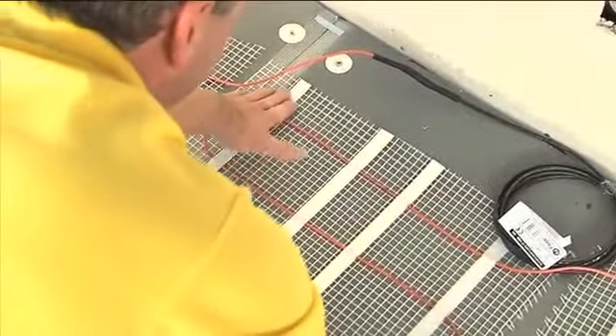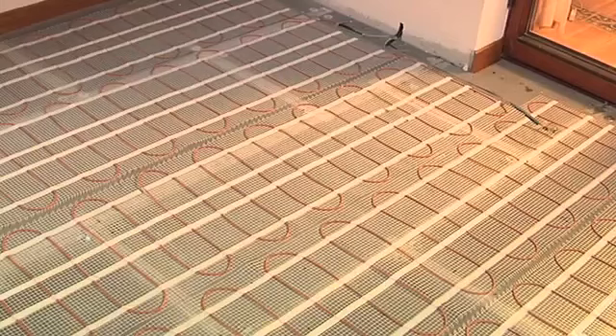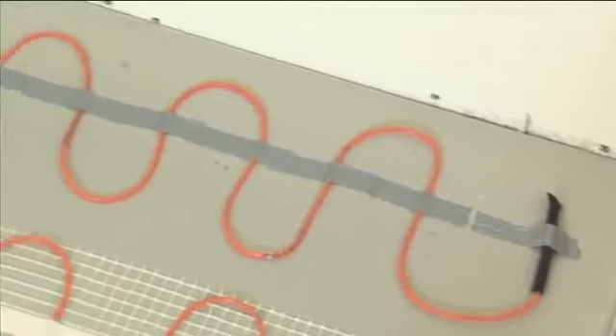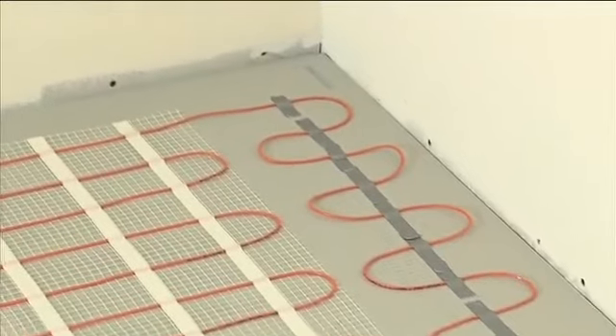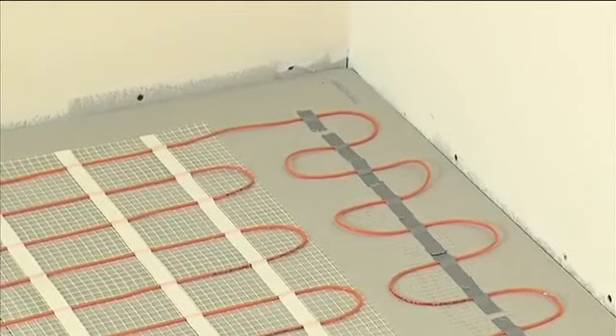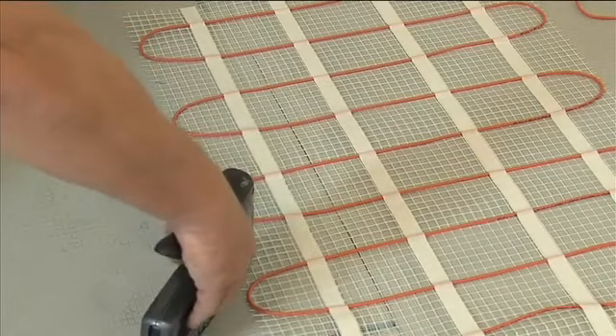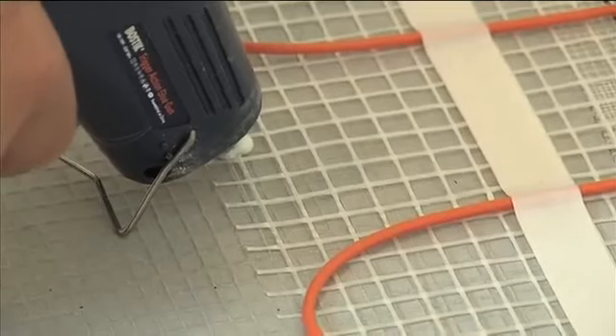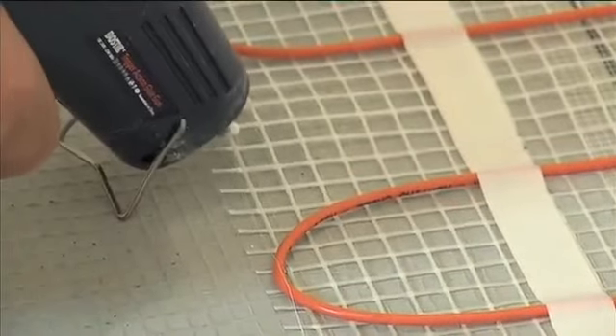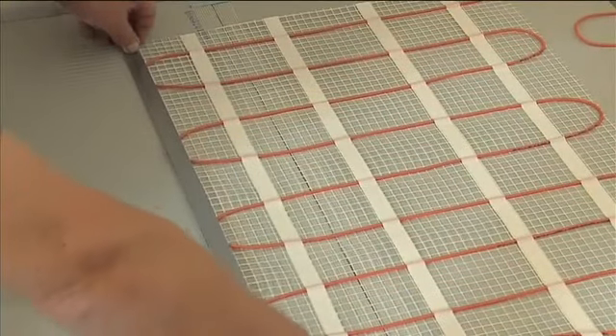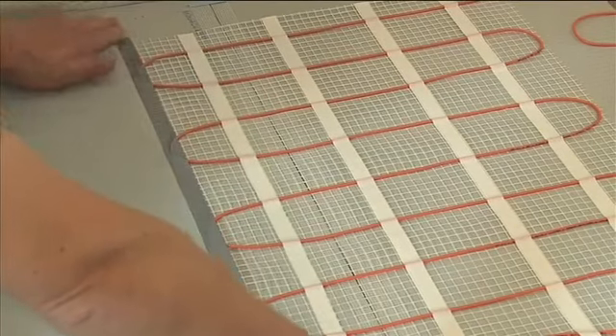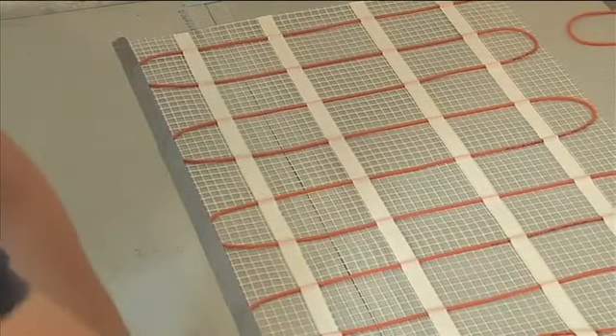Final mat layout should appear neat and tidy, with cables evenly spaced across the total floor. For areas that will not accommodate the floor mat width of 500 mm, the cable can be removed from the matting and attached to the floor uniformly with adhesive fixing tape. The matting can be further secured to the floor by staple gun, hot glue gun, or adhesive tape. This is recommended on the outer edges of the matting when using self-leveling compound to prevent the matting lifting. These additional fixing methods should only be used on the matting mesh and not on the cable.